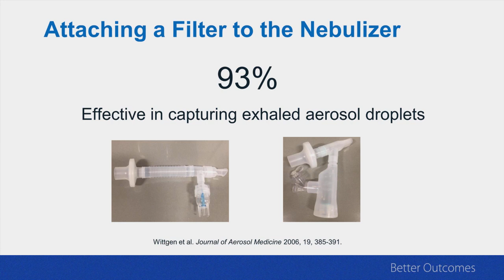However, there is something you need to be careful about with this one. There is an exhalation valve located in the mouthpiece. So you should not block the exhalation valve with the placement of the filter. How are you going to avoid this situation? It's easy. If you have a 22 millimeter silicone adapter in your unit, use it between the filter and the mouthpiece, and that will solve the problem. I didn't have that adapter in my research lab. That's why I couldn't use it when I took those pictures for you. But if you have it, use it with the mesh nebulizer. Also, I recommend that you use a HEPA filter with nebulizers if you can, because they will be much more efficient than regular bacteria filters.